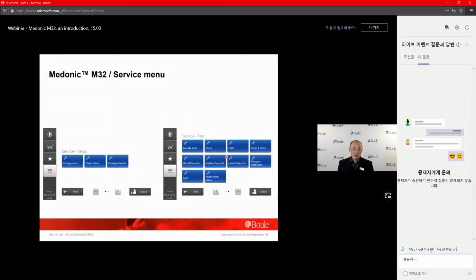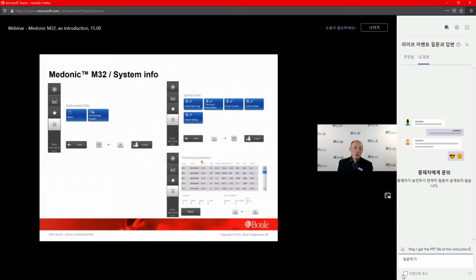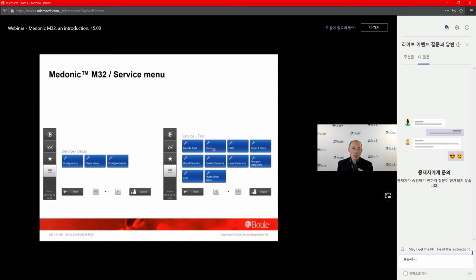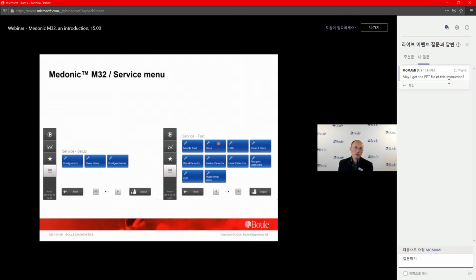The Service menu is very useful for troubleshooting and also to check the instrument status. Here we can do, for example, each component of instrument test, pump and valve test, and also see if there is environmental interference noise from other instruments or from bad grounding.